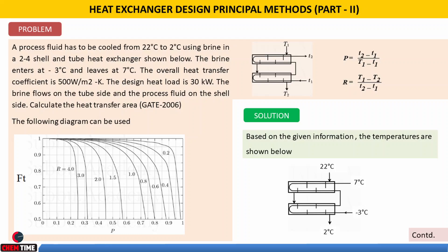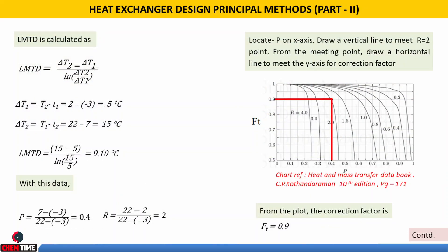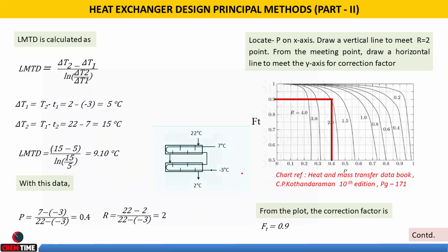With this, we can calculate the logarithmic mean temperature difference (LMTD): (ΔT2 − ΔT1) / ln(ΔT2/ΔT1). Here ΔT2 is the end difference 22 − 7 = 15, and ΔT1 is the end difference 2 − (−3) = 5. So the LMTD is (15 − 5) / ln(15/5) = 9.1°C.